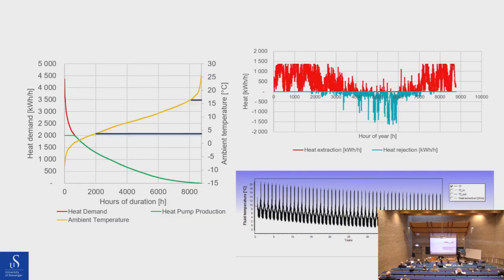I would also like to point out that in Stavanger, it's never really cold and it's never really very warm. So it's about 6,000 hours per year where the ambient temperature is between 4 and perhaps 16 degrees. Then the heat demand isn't that large, and we can utilize the coolers on the roof instead of the boreholes, because you get the same or better temperature conditions, or you can actually throw heat from the air down into the ground.